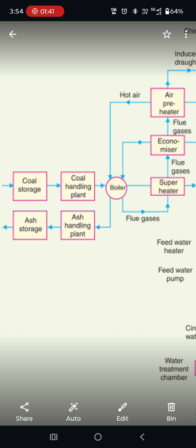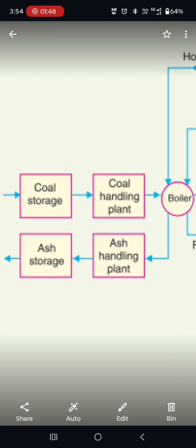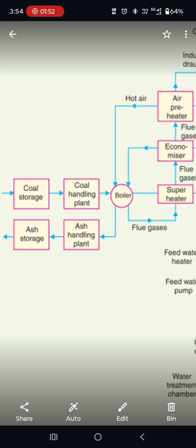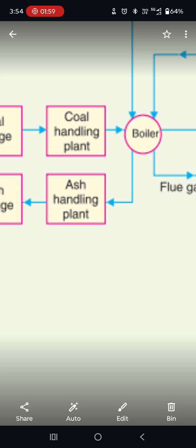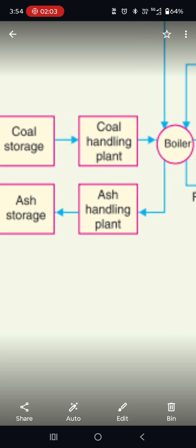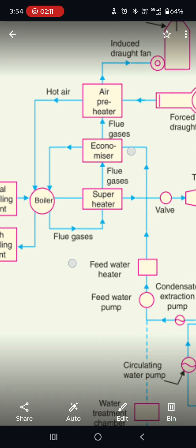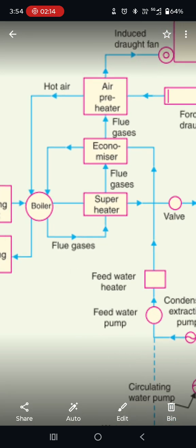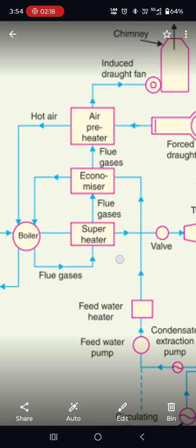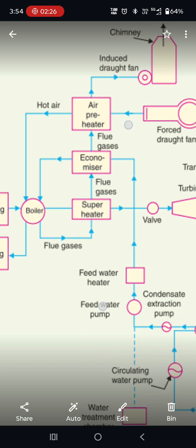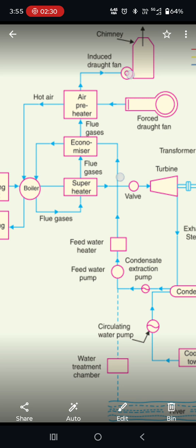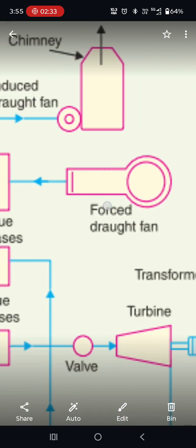We'll see the main components. Okay, first one is the boiler. In this boiler we will supply the coal. There is a coal storage department and coal handling plant. In this coal handling plant, I will explain it later. Then you can see that after the boiler, ash is generated. Ash is treated in ash handling plant and sent to the ash storage. Next you can see that after the boiler there is a superheater which heats the steam up to the 545 degrees centigrade. Then economizer, air preheater, and after air preheater you can see that here, induced draft fan and chimney.